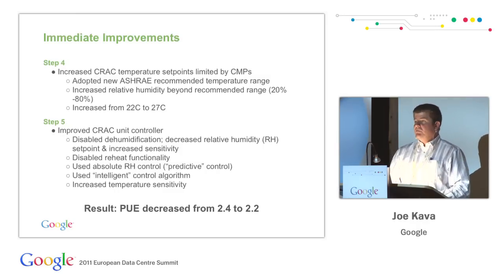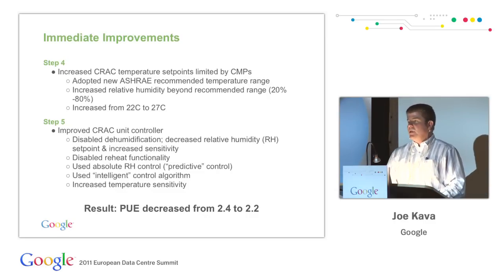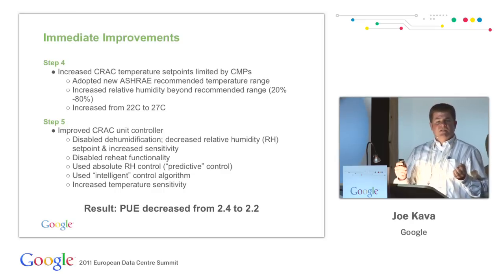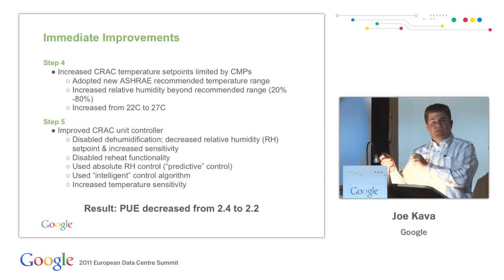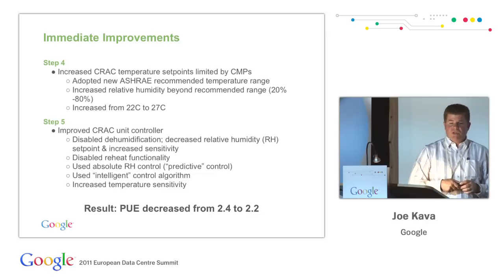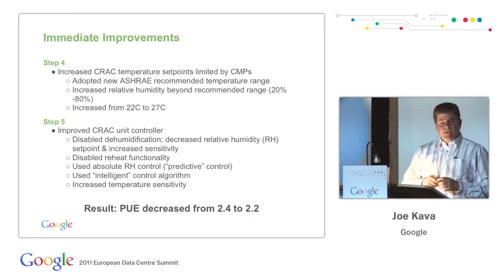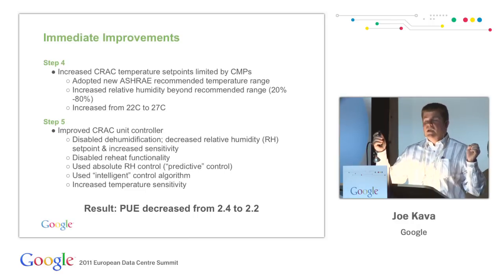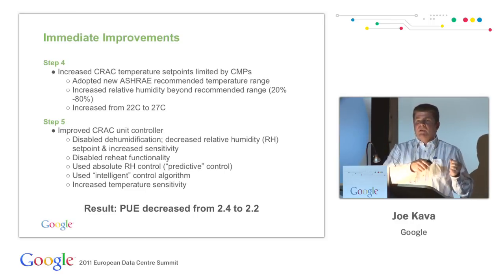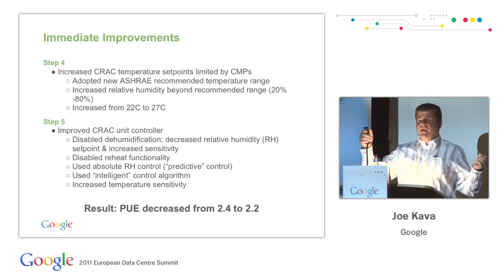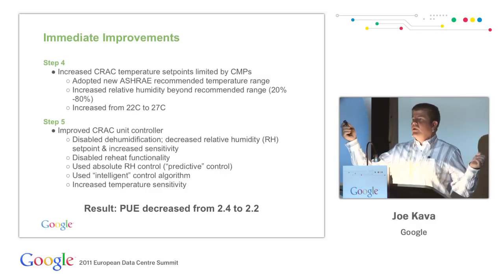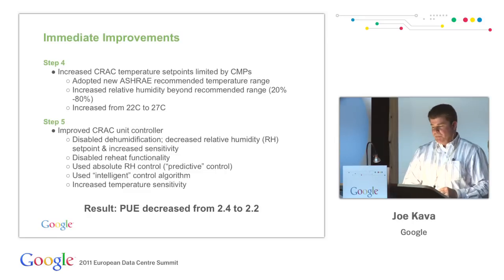Next, we increased the CRAC set point. So we went and turned up the thermostat. We now set it to 27 degrees, where it previously had a set point of 22 degrees. And lastly, we implemented improvements in the functionality of the CRACs. I had mentioned that they were set to local control, to humidify and dehumidify. So we disabled the dehumidification, and we decreased the relative humidity set point and increased the sensitivity so that they didn't turn up compressors as quickly as before. They would allow a higher operating range before they increased more mechanical cooling.